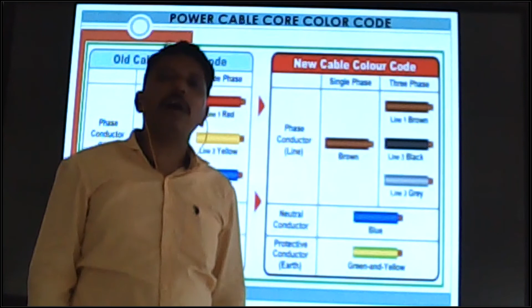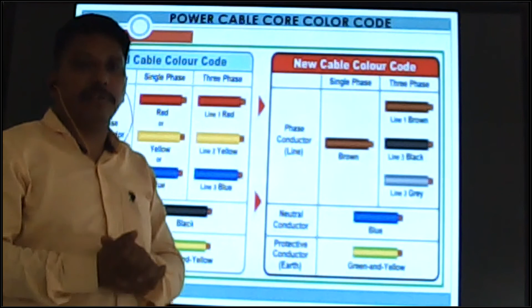And in the new color code, brown is used for single phase, and blue is used for neutral, and green and yellow, green is used for earthing. Earthing is the same. Here the only difference is two things. Okay. Black in the old color code is used for neutral, and in the new color code, black is used for line 2. Only this is the difference. So don't confuse this one. You can remove the insulation of the cable and check the core color code inside. As per this, you can do the termination. Very easy formula, this one. You can use this formula. Okay. No problem for you. You can check the cable, do like that.